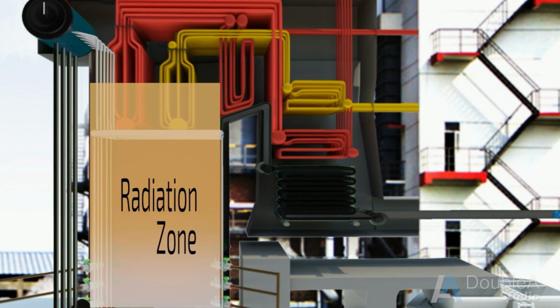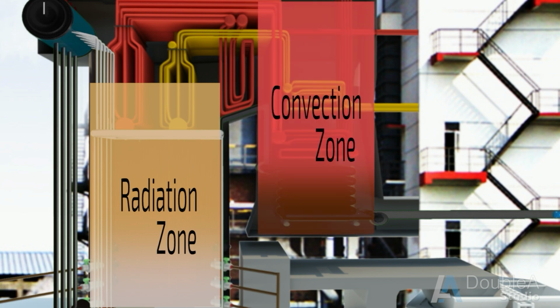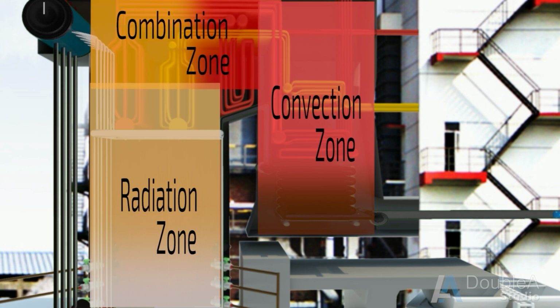First is the radiation zone, where heat is transferred through thermal emission. So this zone is around the furnace where coal is burnt. Second is the convection zone, where heat is transferred by the movement of hot flue gases. So this area comes under the convection zone. Third zone is a combination of two, that is radiation plus convection, and therefore comes between the two.